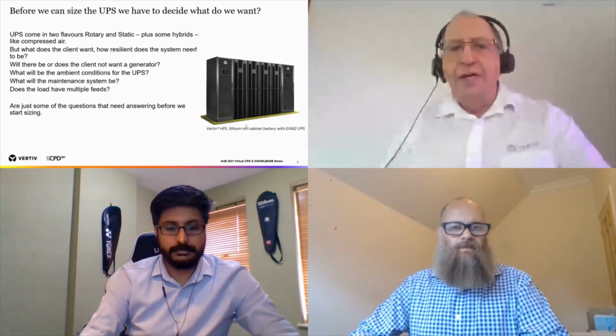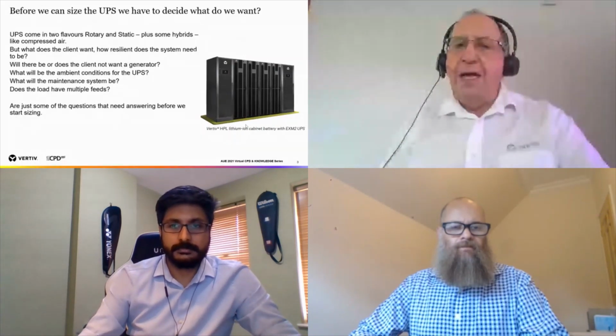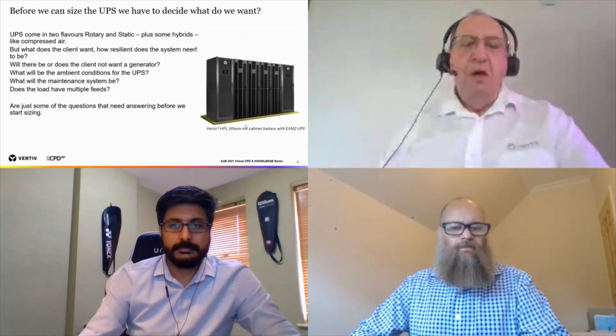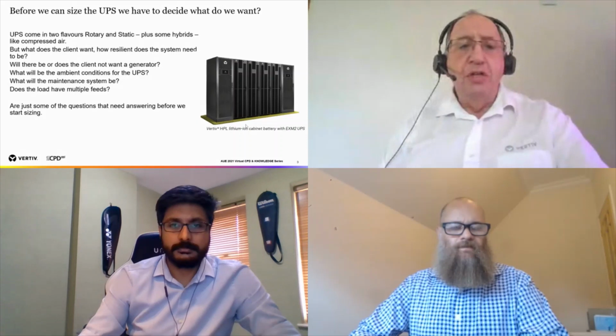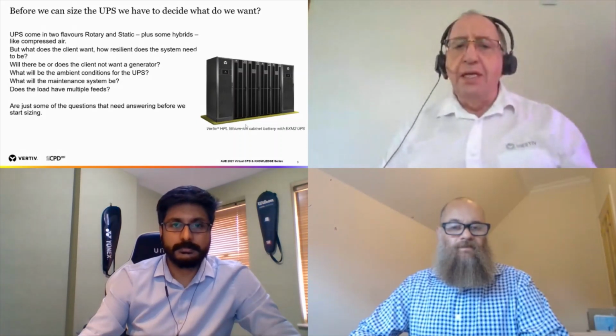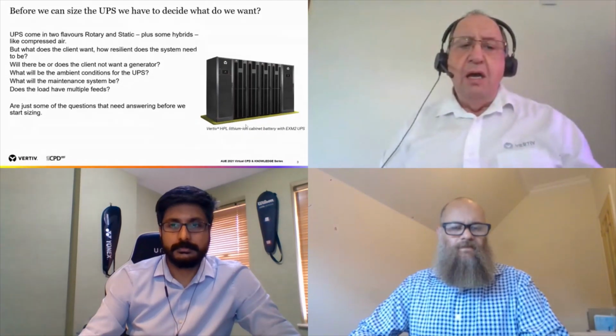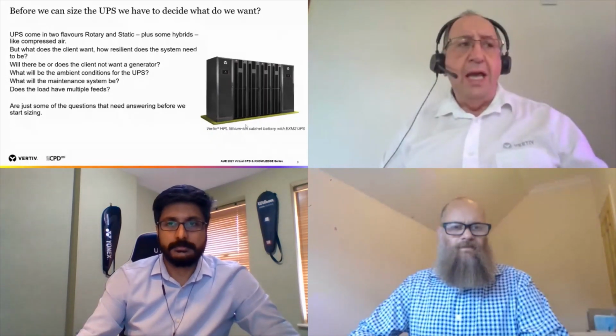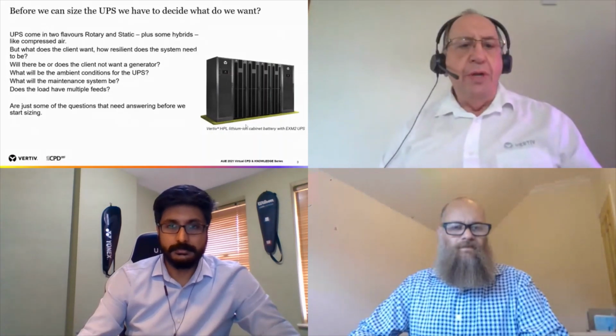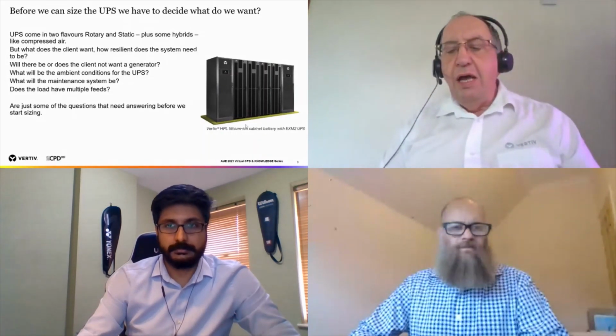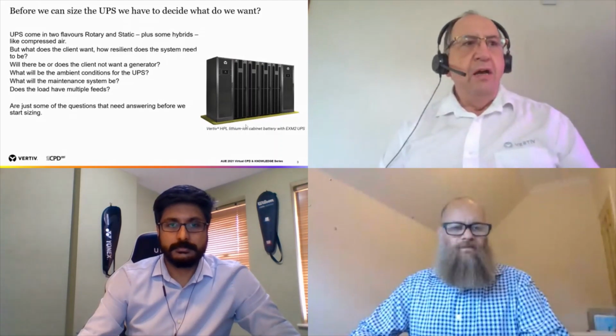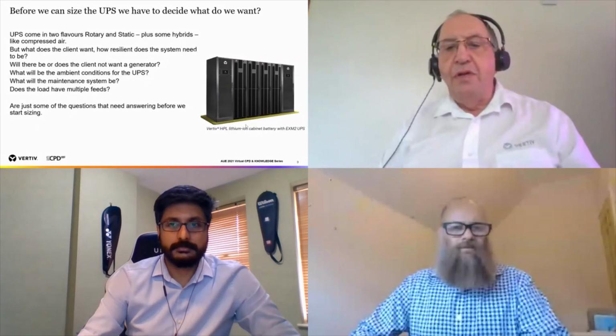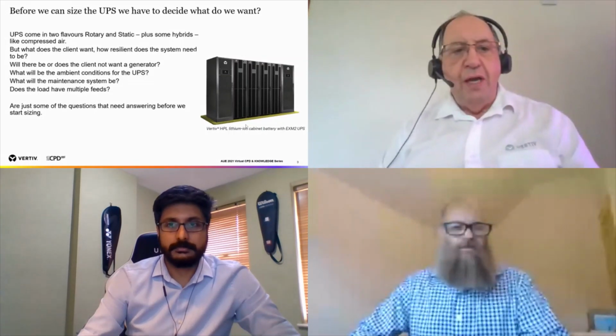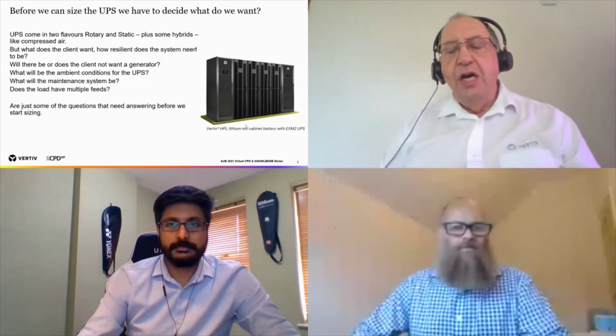A lot of clients nowadays don't want generators, and that could mean that we have to look at hybrid battery systems. What are the UPS ambient conditions? The UPS doesn't need the same ambient conditions as the generator in modern designs, so they can be in two separate places to save money. What will the maintenance system be? If we're dealing with a campus in Malaysia or Borneo or whatever, what sort of maintenance would you require? And in particular, whether you're going to need a watch system. We have a system where we have 24/7 coverage available on UPSs and generators, etc. They're just some of the questions that we need to consider.